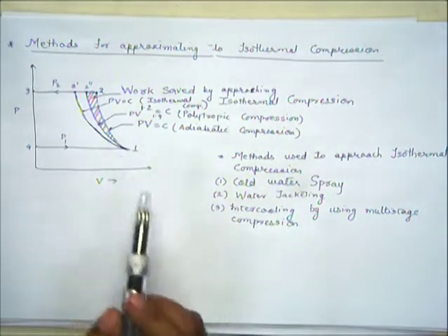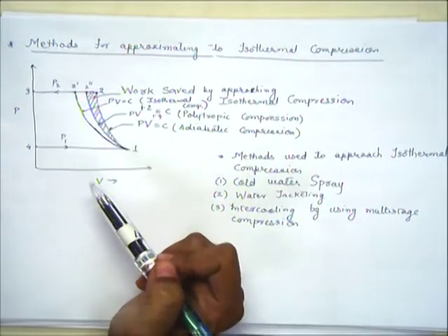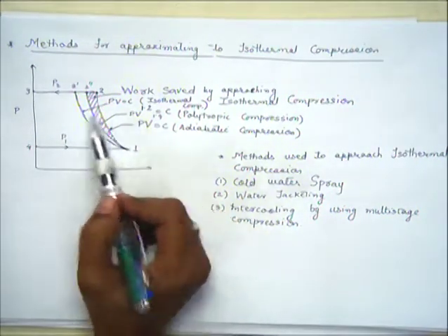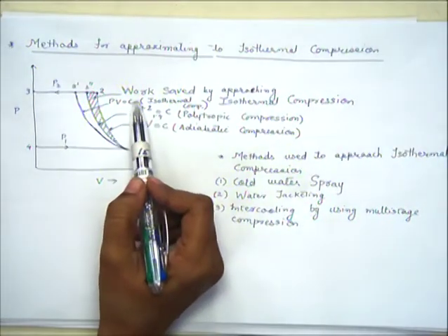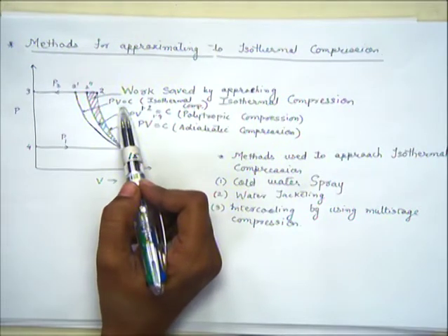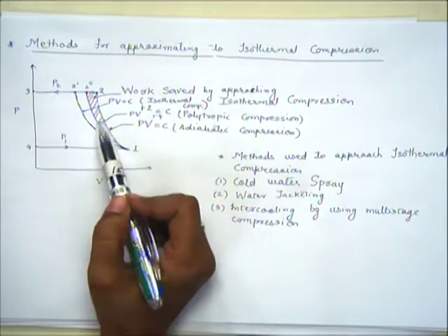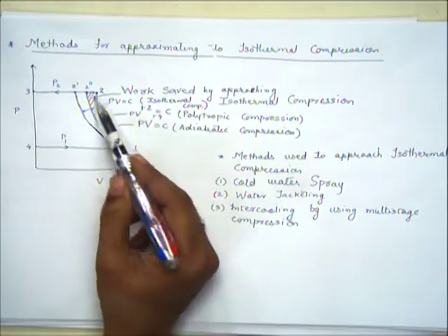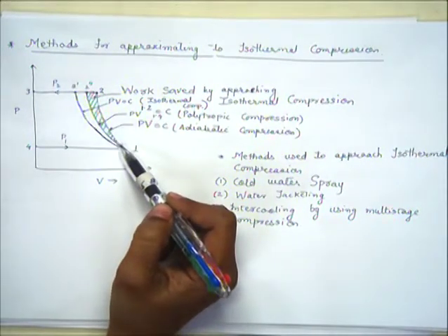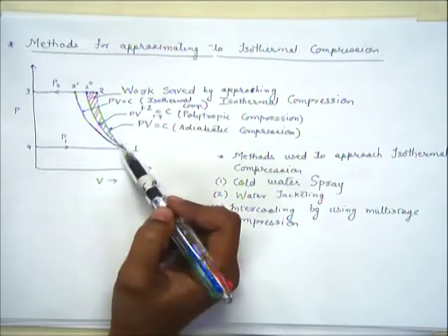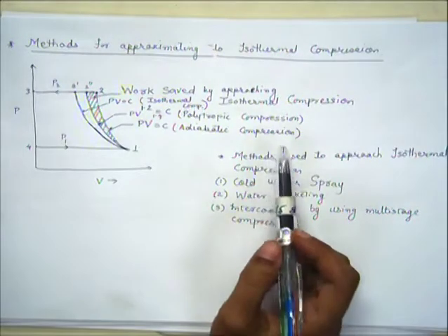On the PV diagram, the line 1-2 shows adiabatic compression where PV^1.4 = constant. The innermost line represents isothermal compression. Ideally it should be isothermal, but we cannot achieve exactly isothermal compression, so what we get is polytropic compression. We can see there is a reduction in work required — shown by the area between the curves. Even if we cannot achieve complete isothermal compression, we can try to approach it by various methods.